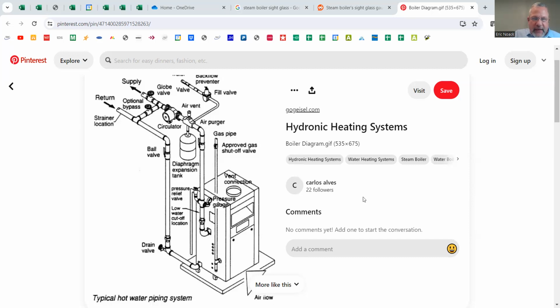But what you're going to see is a blowdown valve, is what they call it. It's a device that's used to kind of wash out the sediment. It's a catch for the sediment. You want to make sure that the water is really clean in one of these. But the other couple of things that you'll see is on a standard hot water boiler, there's almost always going to be a circulating pump, okay?